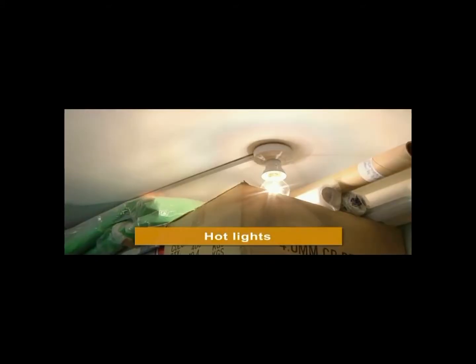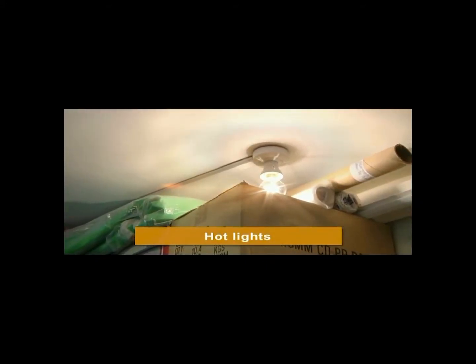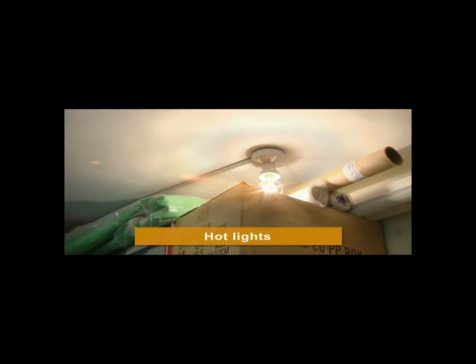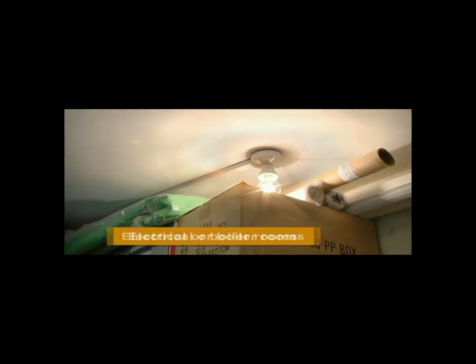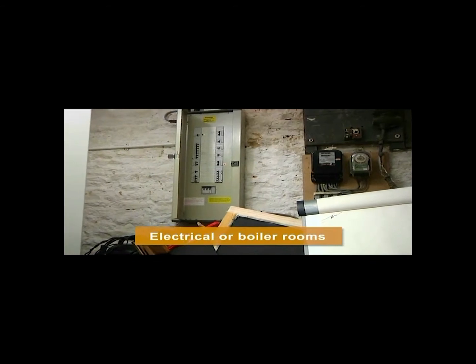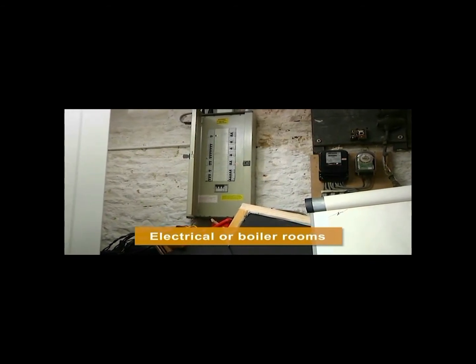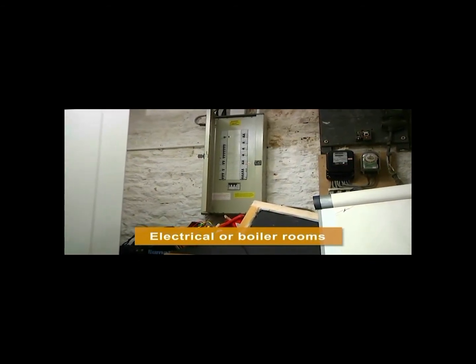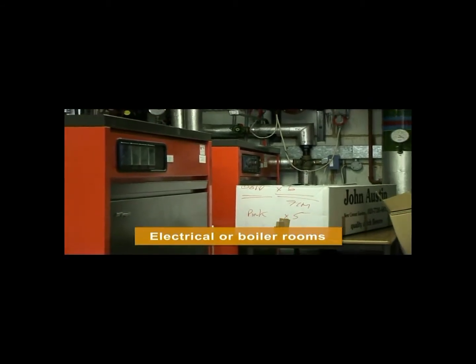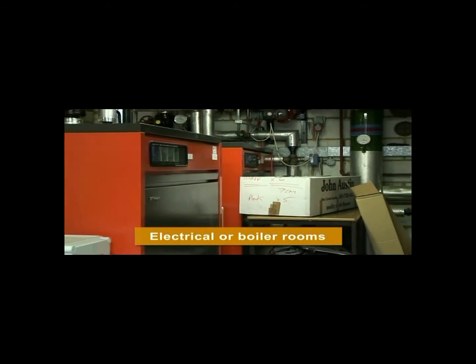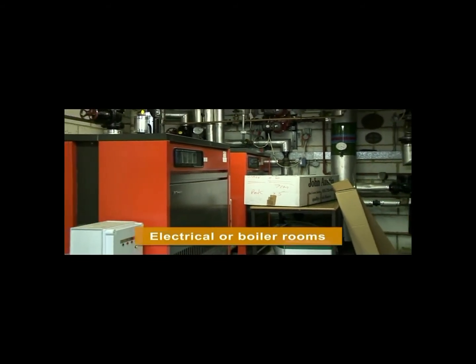Don't store anything close to lights, and if possible replace hot lights with cooler running lights. Ensure that combustible materials are not stored in rooms with electrical equipment like fuse boards or plant. Similarly, combustible or flammable items should never be stored adjacent to boilers or in boiler rooms.